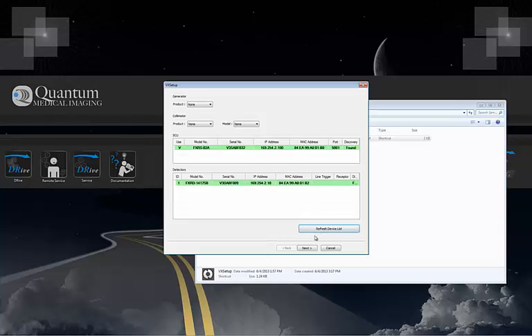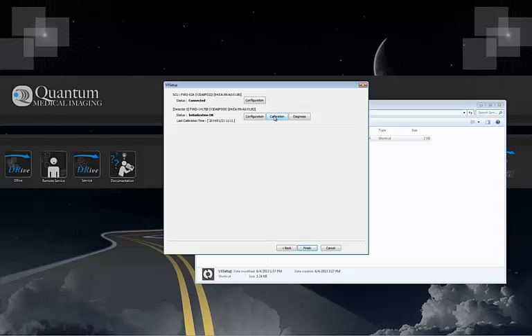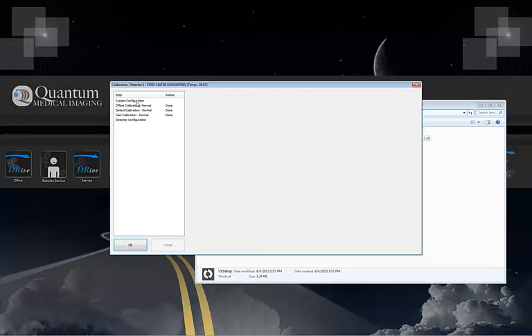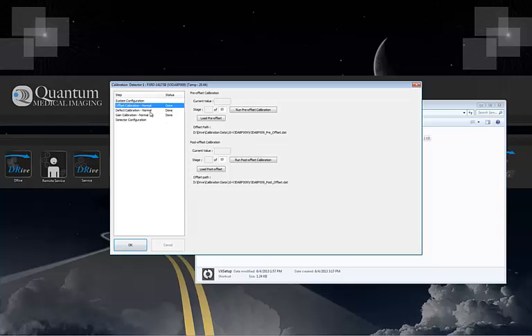The next button brings you to the detector calibration, and under the system config is where you set your detector for either hardwired trigger mode required for your quantum generator integration or the automatic exposure mode for bundling with some other manufacturer's generator. Note also the exposure section should be set for 800 milliseconds.